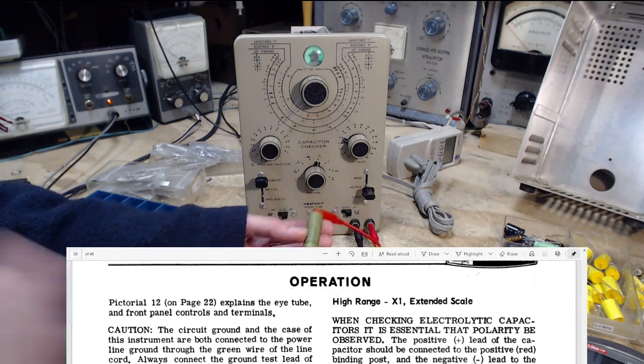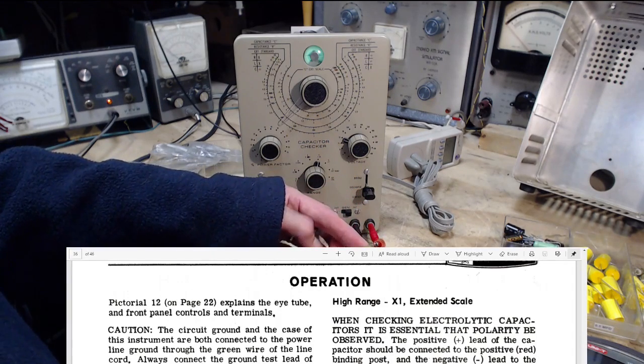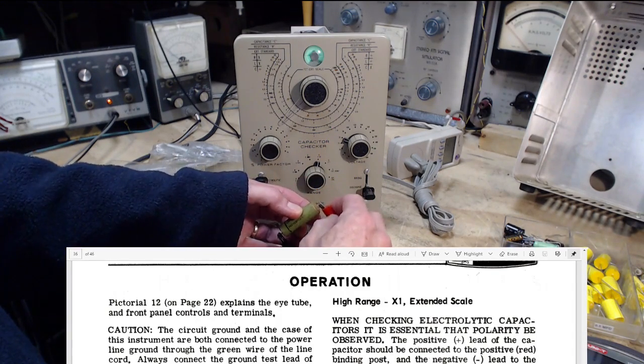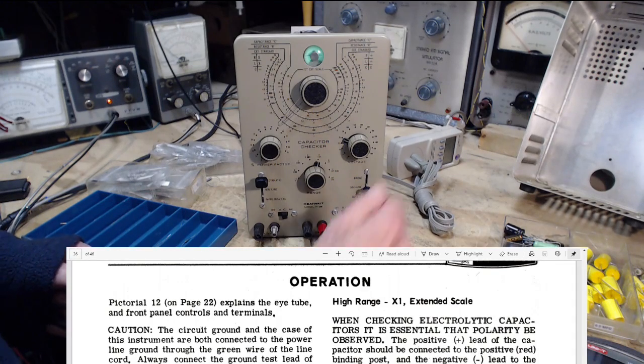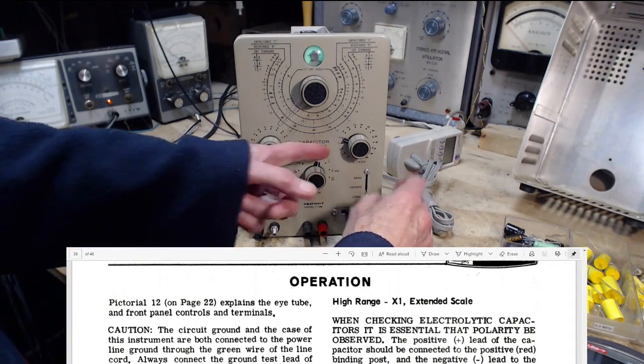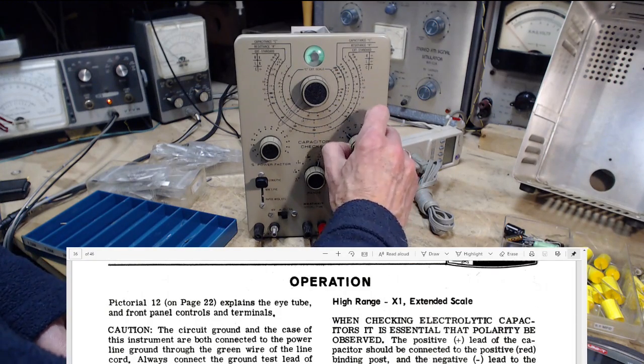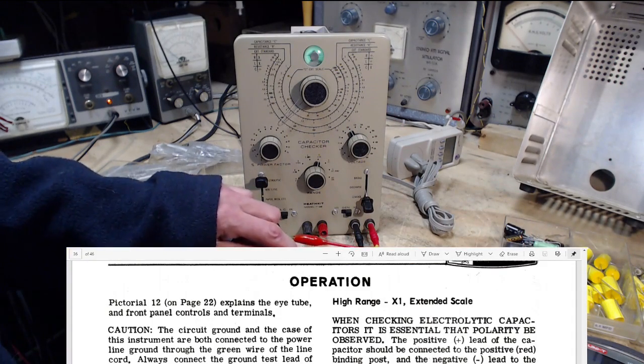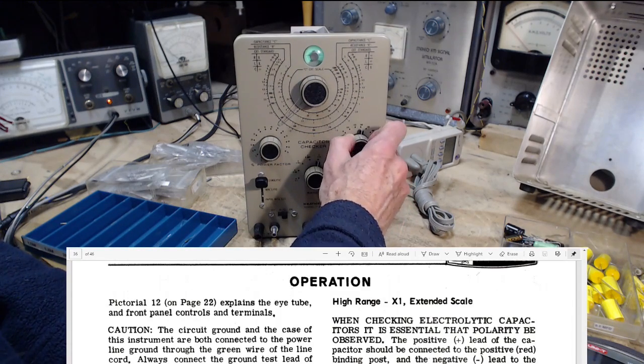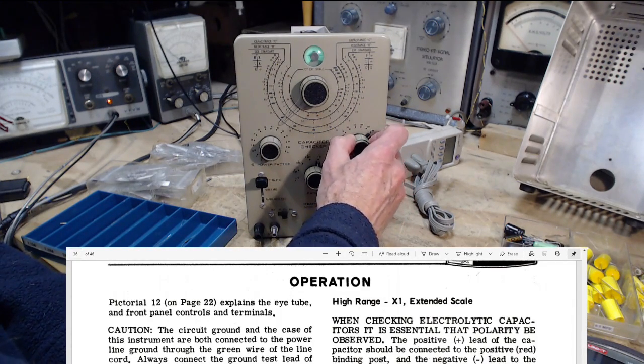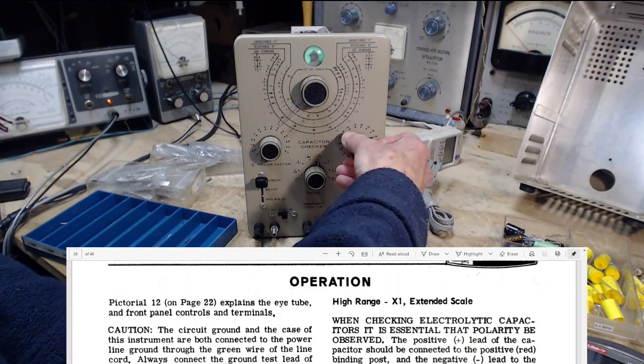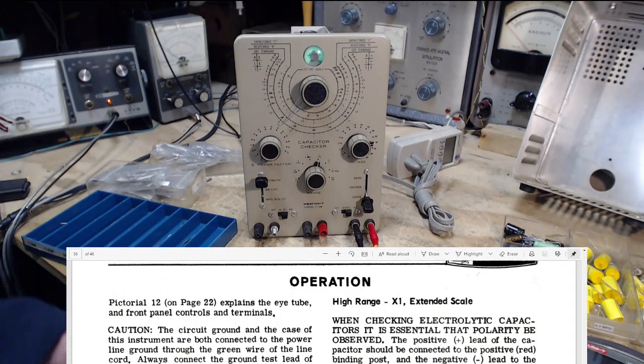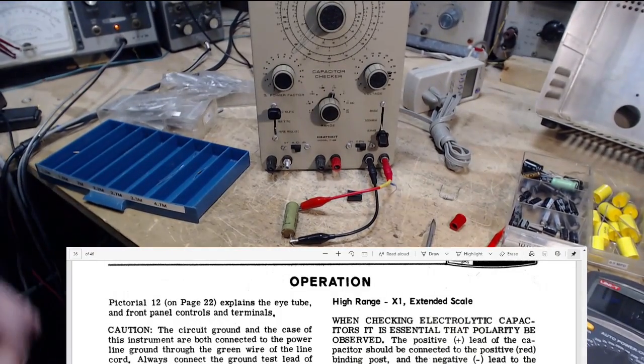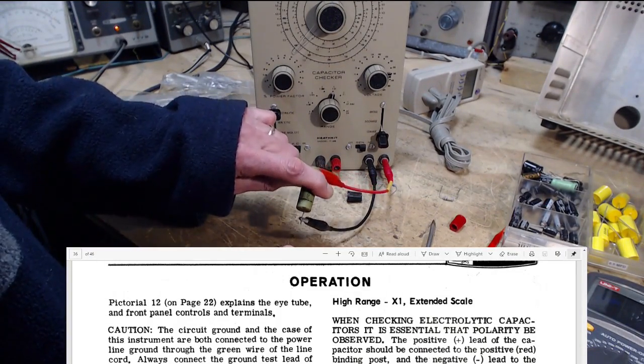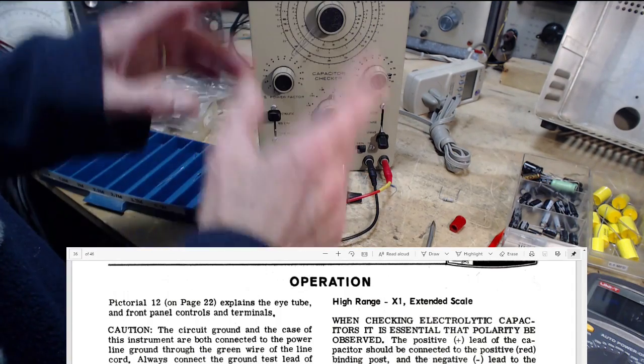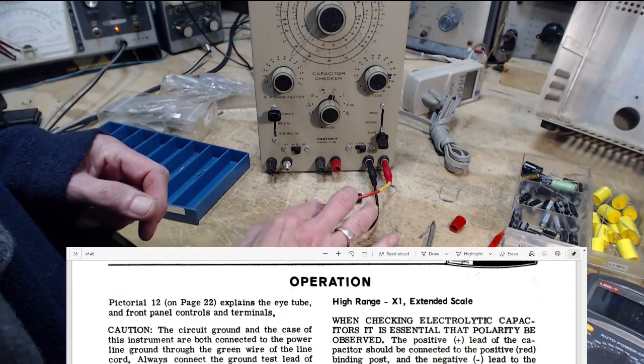Another oldie. 0.05. Leakage: good at 25, good at 50, good at 100 — have I got it hooked up? 150, no leak in this thing? Come on, really? 350. 400. What? There'd be smoke coming out of it by now. So I didn't see any charge up or anything.